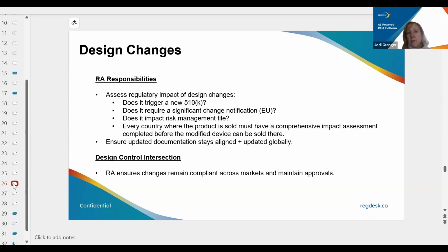Change control may also, even if there's not a submission that's required as the impact, you need to make sure that your documentation stays aligned and that it's updated globally. So your tech doc for Europe, of course, is dynamic. So as things are changing, even if it's not something that you need to submit for approval before implementing, you need to make sure that your tech doc is up to speed and revised accordingly. So regulatory's role is to ensure that all changes allow your product to remain compliant across markets, and that you maintain approvals in each of those areas.